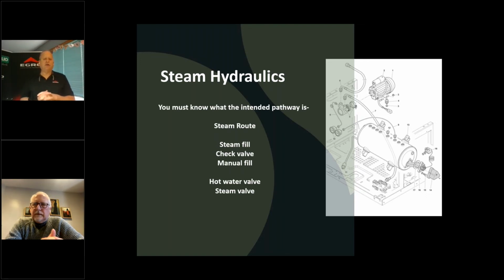Then on some machines you also have a manual fill. On this one, it's right here. I'm a big proponent, by the way, of not opening a valve that has not been opened in a long time. So I tend to stay away from any valve that's not a manual fill valve, or even a valve at the wall. I don't like opening it and closing it if it hasn't been moved in 35 years. Then we've got a hot water valve, which we talked about earlier. I've got a dual one here, but you can have a single one, and typically we're not going to have too many problems with that. If we have too much scale, we can get scale into this valve, but typically it's going to exhibit itself at the spout.